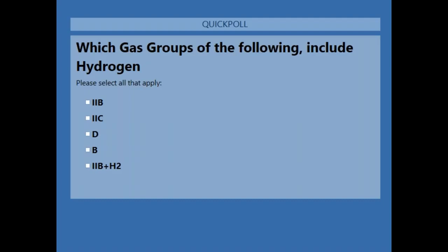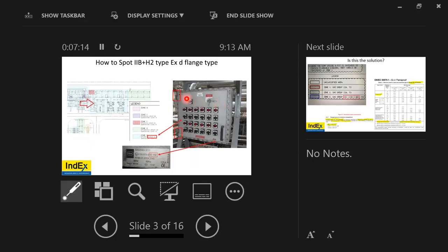Okay, so when we go into further detail and look at this device, things that we notice are these right here, the hinges, would indicate this is not a 2C piece of equipment. When it comes to 2C equipment, we're talking about very tight tolerances that do not allow for the use of hinges.